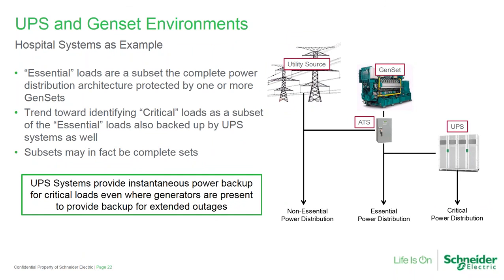Less defined by code, or arguably not defined at all, would be what additional loads require protection for the period it takes generators to come on—that might be 8 to 20 seconds depending on the system, and by code in hospitals it's 10 seconds or less. Hospitals typically define a subset of those essential loads that also require UPS backup for bridge power, the time it takes for generators to come on.